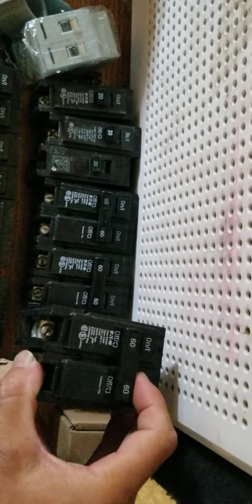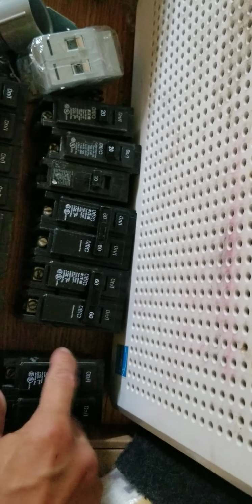The code for San Diego, California for a duplex or apartment unit is 240 volt, and each hot wire is 60 amp. So the breaker can be used for 60 amp - a double breaker 60 amp, one side is 120 and the other side is 120, which together is 240.